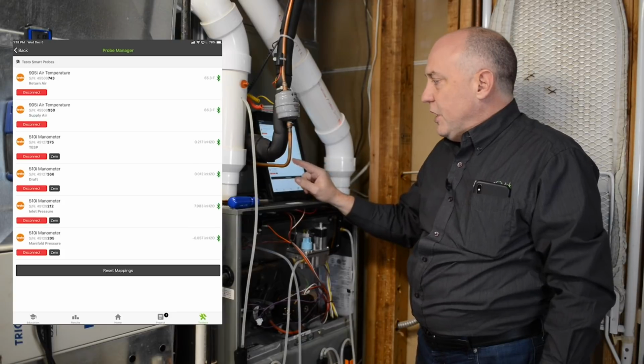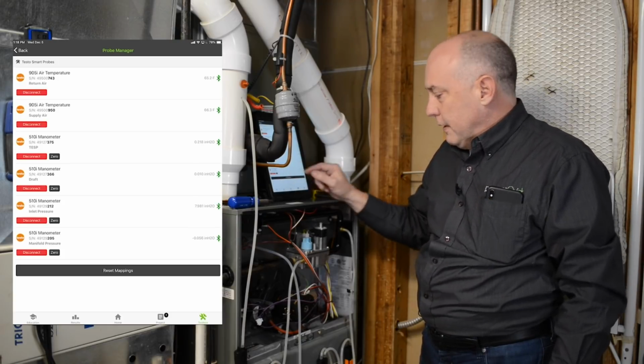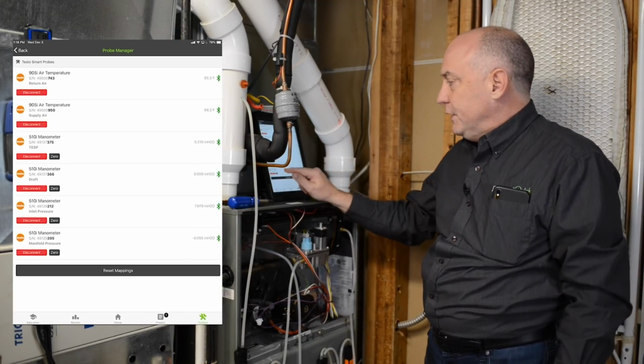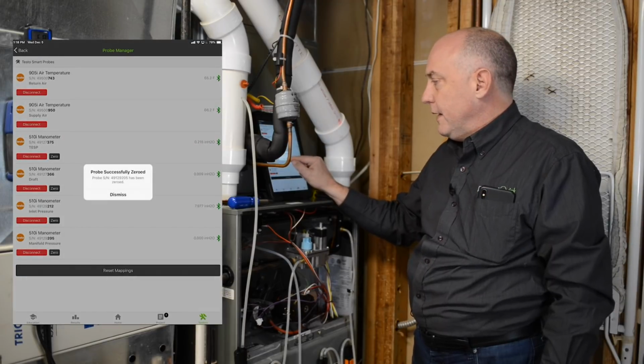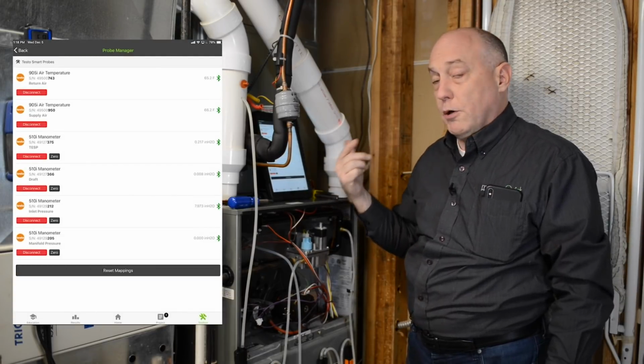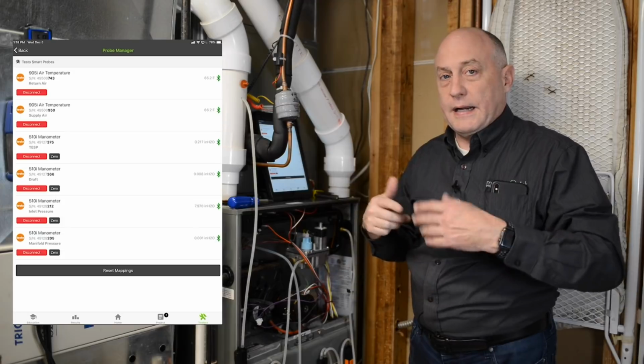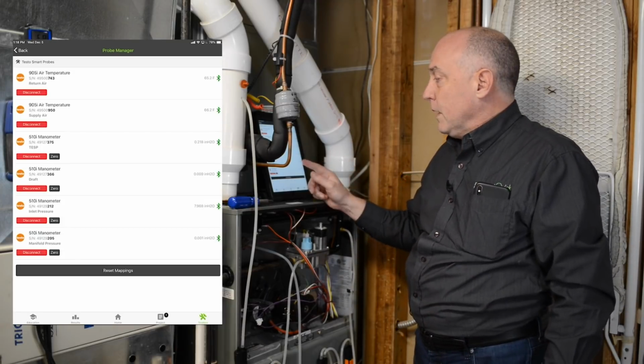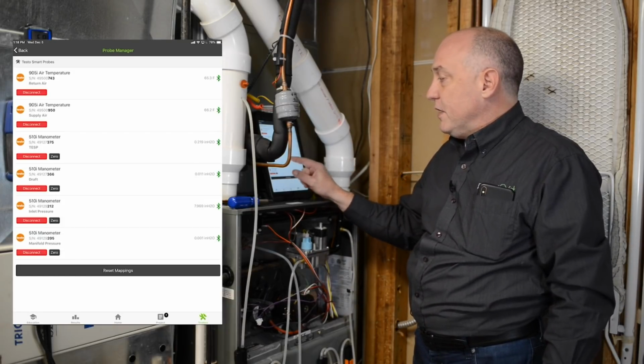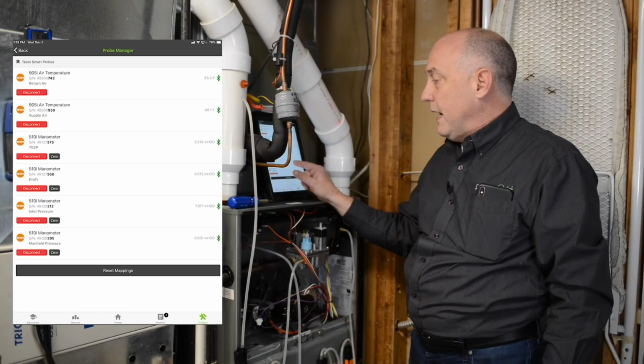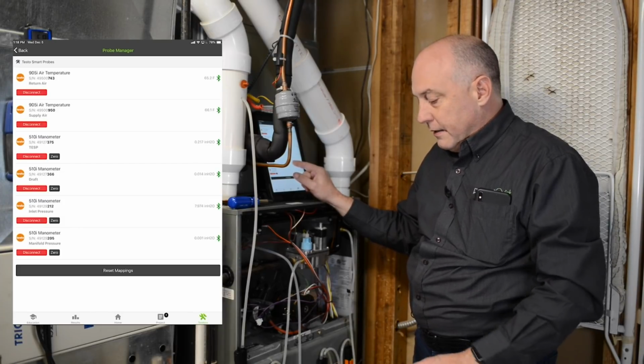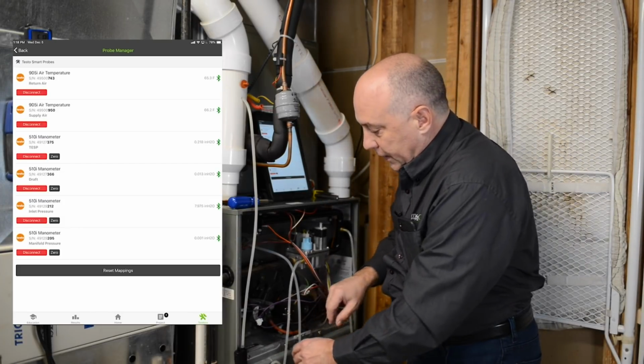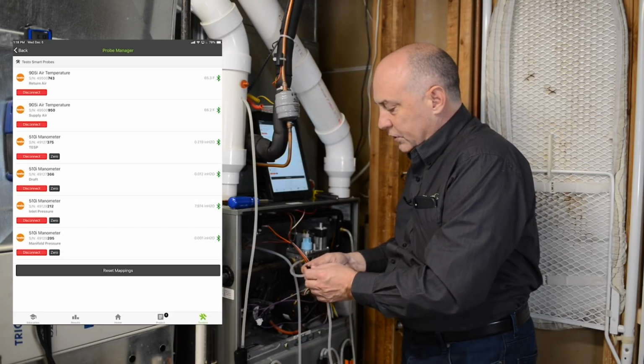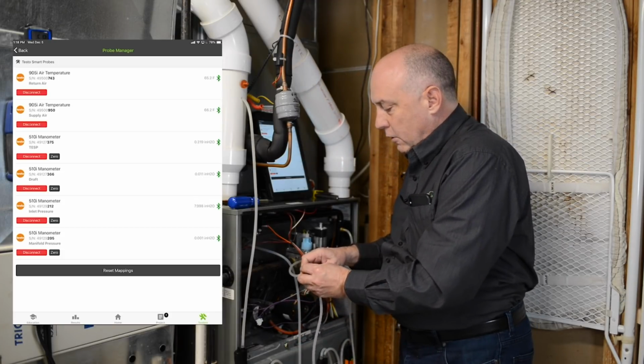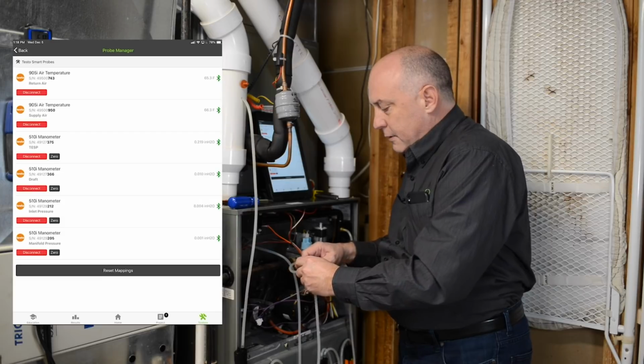Now I'm going to go ahead and check my manifold pressure, and obviously there's no flame on this now, so I'm just going to hit 0 here and zero that probe out. It says the probe's successfully zeroed, and then I hit the dismiss key, and that's that. And you can zero these at any one time. You can see I've got my inlet pressure at 7.9 inches of water column. That probe, when it came on there, I'll go ahead and pinch this off for just a minute. We'll zero that just to see how close that holds at 0, because it's been a little while since I've zeroed these out.